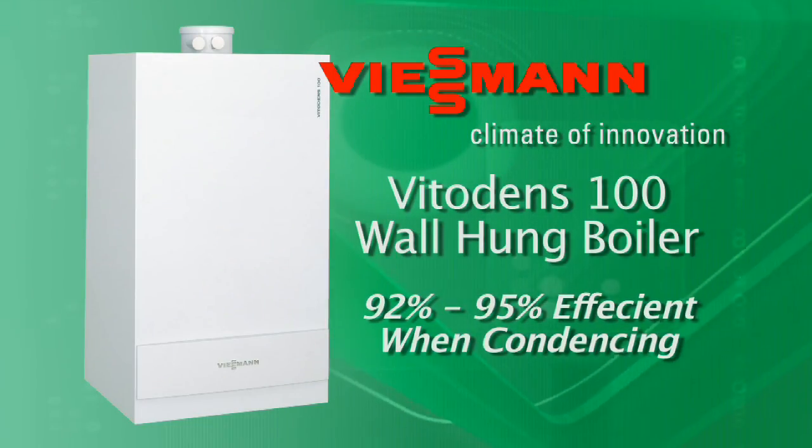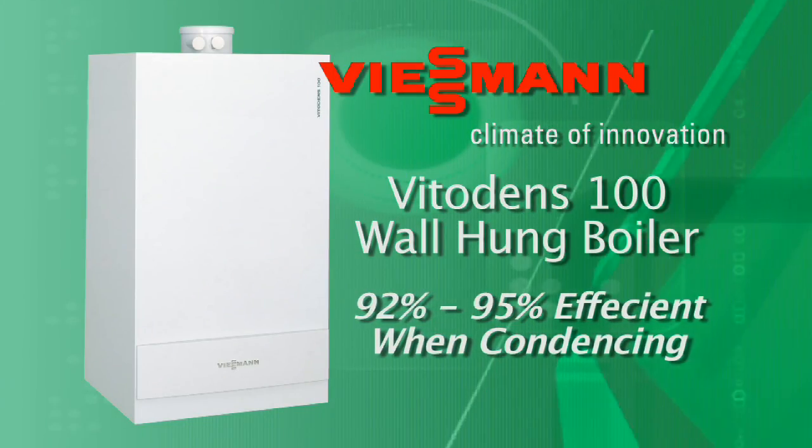You're keeping the heat in the appliance and in the home longer and using it more efficiently. So when the Viessmann Vitodens is condensing, what type of efficiency are we going to expect? You're looking anywhere between 92 and 95 percent, depending on the outdoor temperature and where you're at — there are some variables. So if we were at 95 percent and I spent one dollar for fuel, I would get 95 cents out of that boiler. Conventional boilers' efficiencies are anywhere from 65 to 75 percent, so for every dollar you feed that boiler, you might get 75 cents.